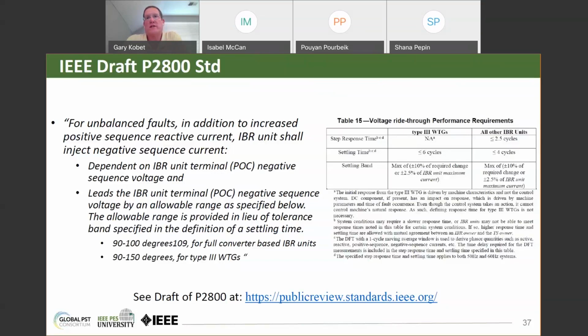And on the right side of this slide, there's a table that specifies voltage ride-through requirements and the step response and settling time and that kind of thing. But the P2800 standard is the industry's, at least IEEE's, attempt at documenting requirements that utilities can use in their discussions with IBR so that the protective relaying that we have out there will actually work. Next slide, please.